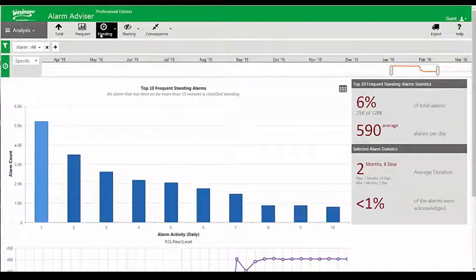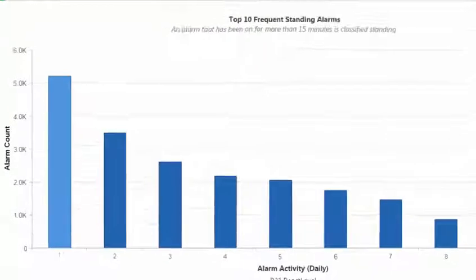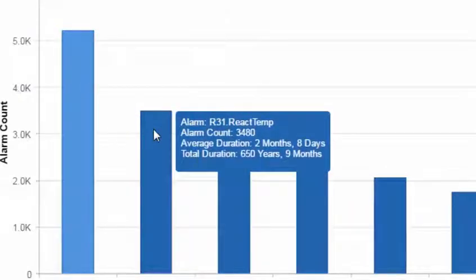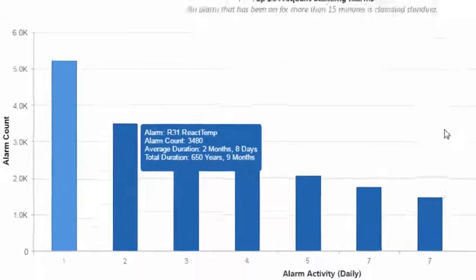The next tool gives me the ability to see standing alarms — alarms that have been on for a long period of time. If I hover over a specific period of time, it tells me how long it's been on and the average duration, so I can understand there are alarms out there that have been active for a long time. Let's go understand what's going on with those alarms and try to fix those problems.